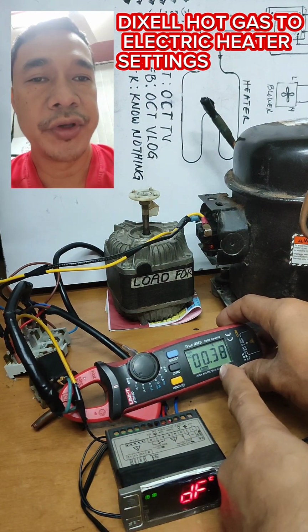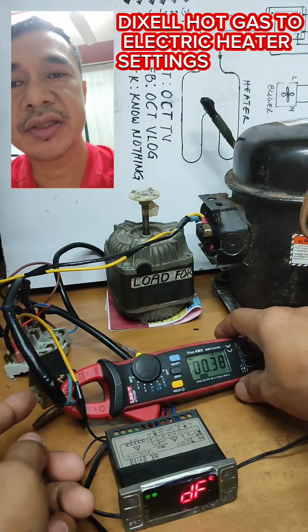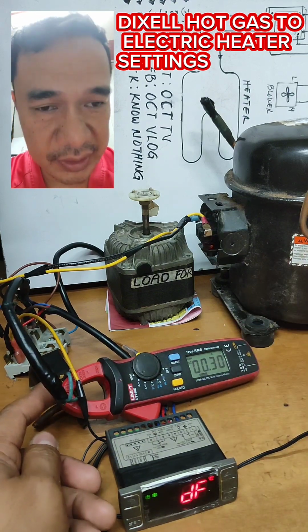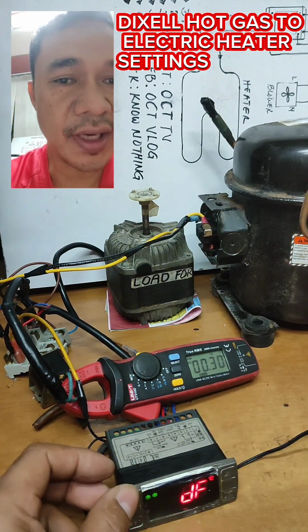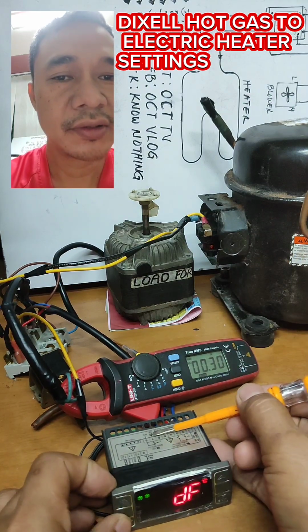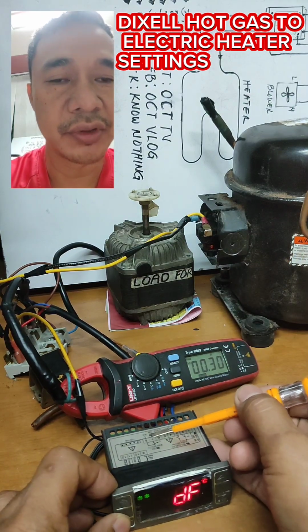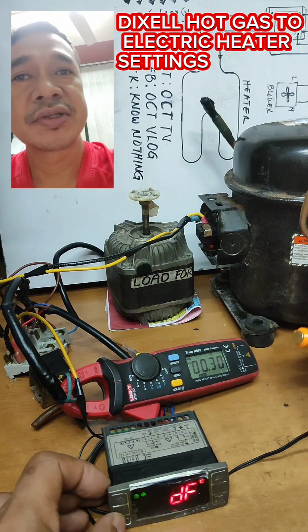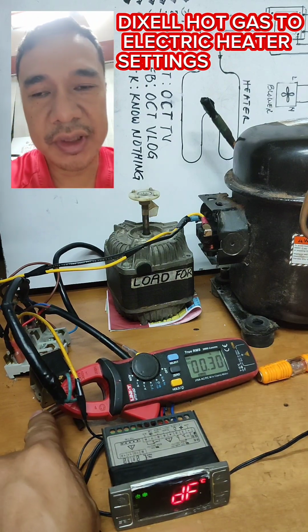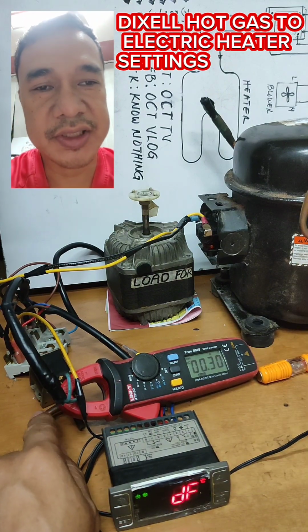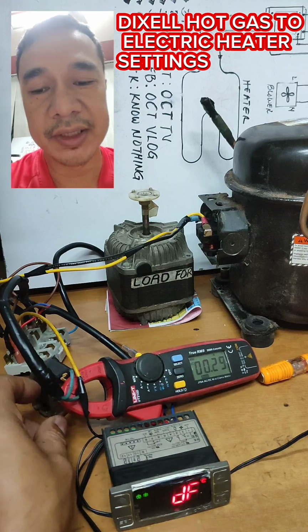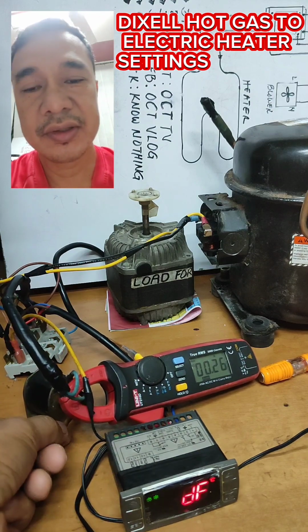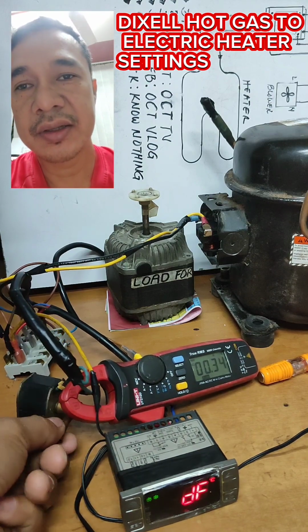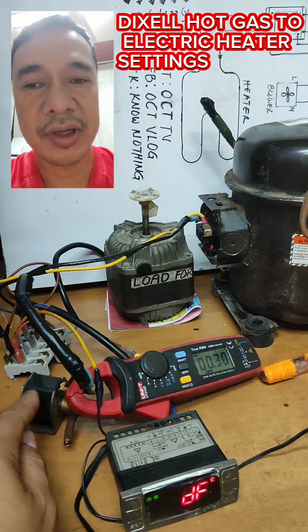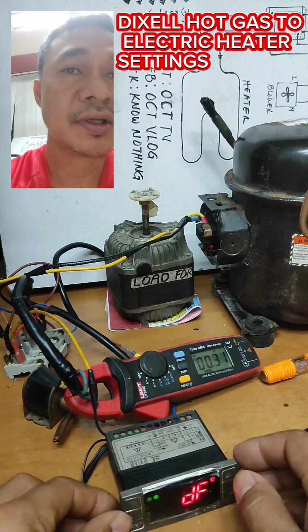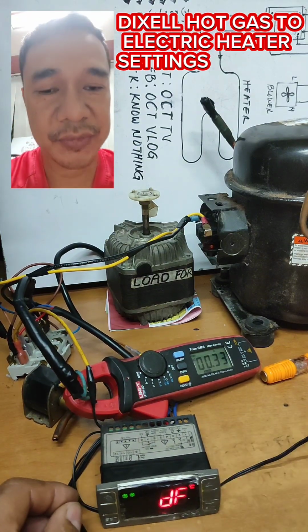We read 0.38 amps here, meaning that the solenoid is activated for the line or terminal number 7, which is our defrost here. So it's shorted, and how am I going to fix the issue while ordering the parts? Okay, there is a process on how to order these parts. So here's a tip, guys, on how to do that.